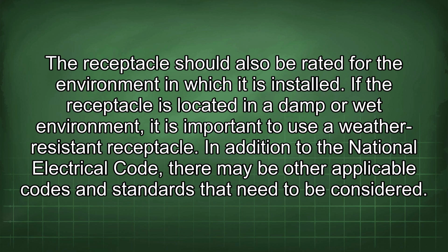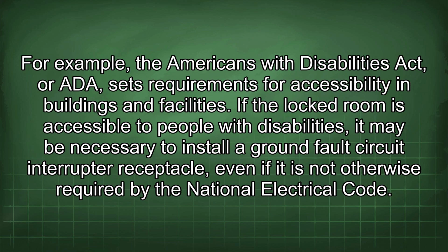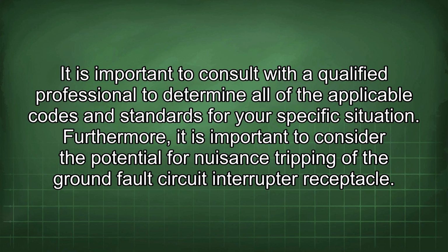In addition to the National Electrical Code, there may be other applicable codes and standards that need to be considered. For example, the Americans with Disabilities Act, or ADA, sets requirements for accessibility in buildings and facilities. If the locked room is accessible to people with disabilities, it may be necessary to install a ground fault circuit interrupter receptacle, even if it is not otherwise required by the National Electrical Code. It is important to consult with a qualified professional to determine all of the applicable codes and standards for your specific situation. Furthermore, it is important to consider the potential for nuisance tripping of the ground fault circuit interrupter receptacle.